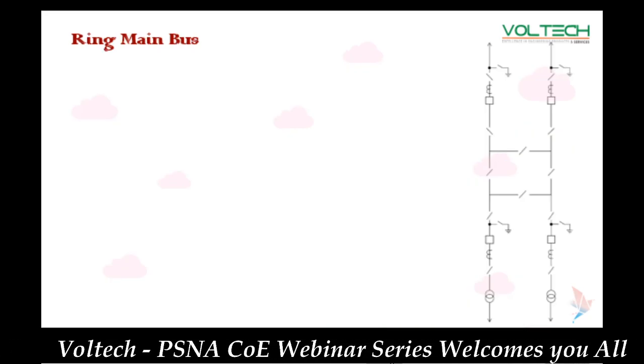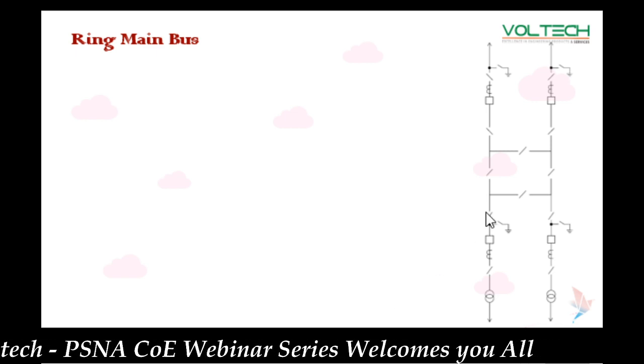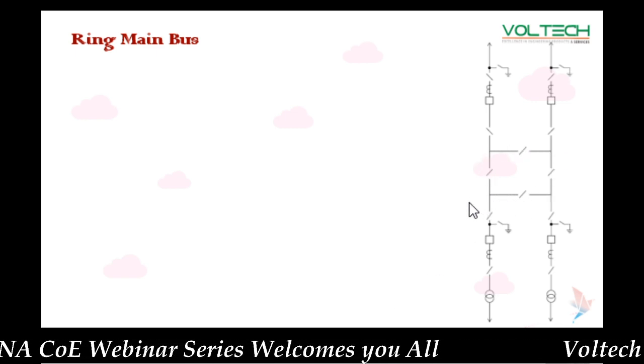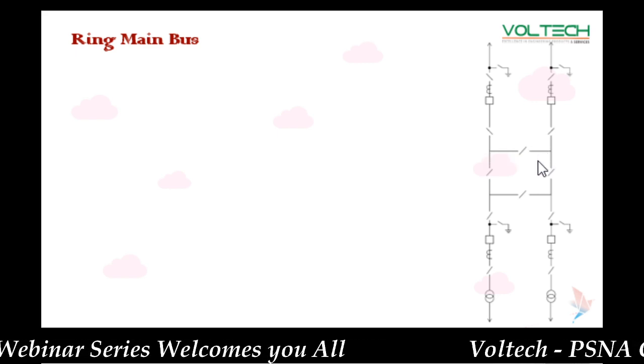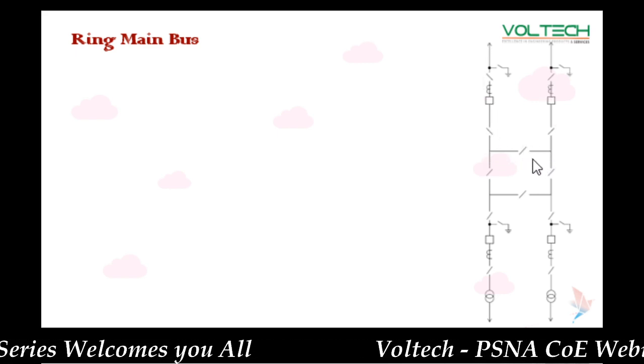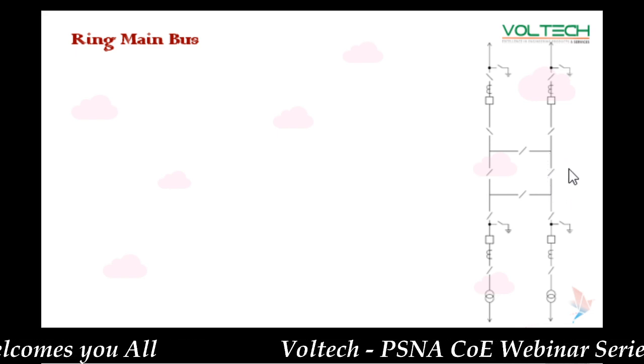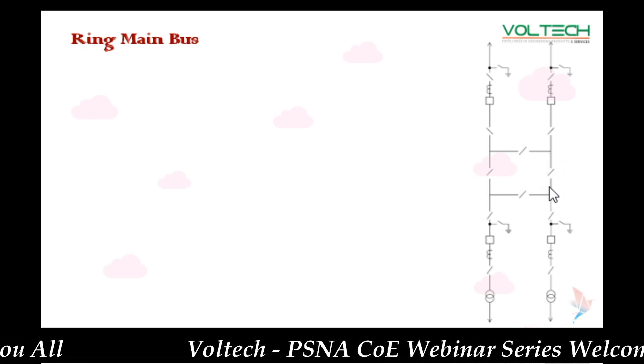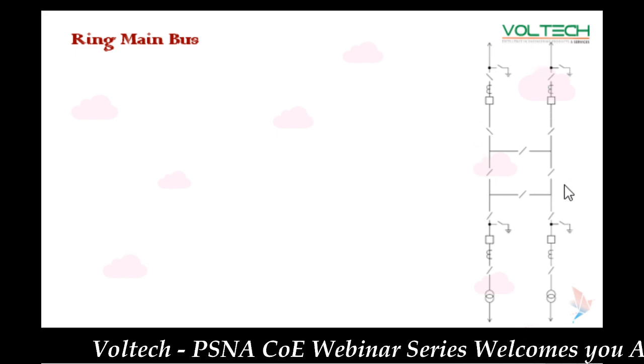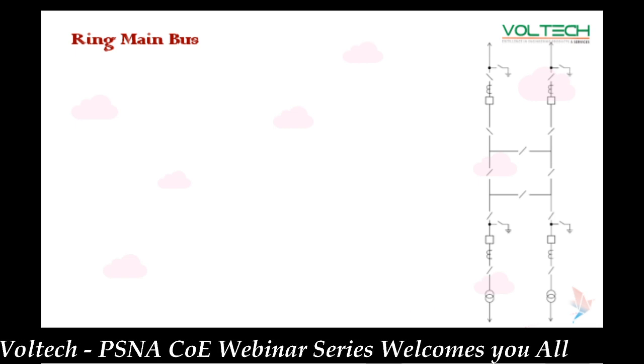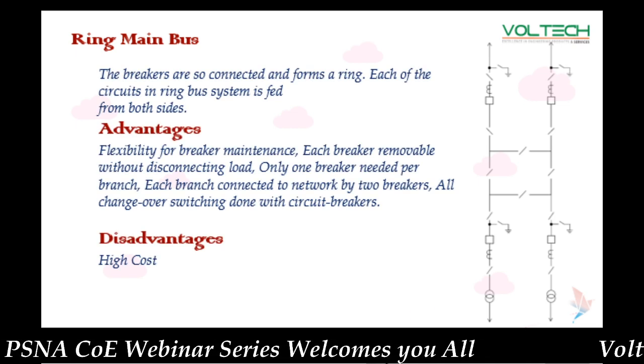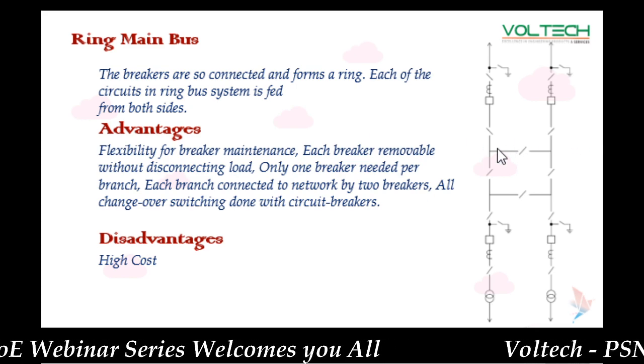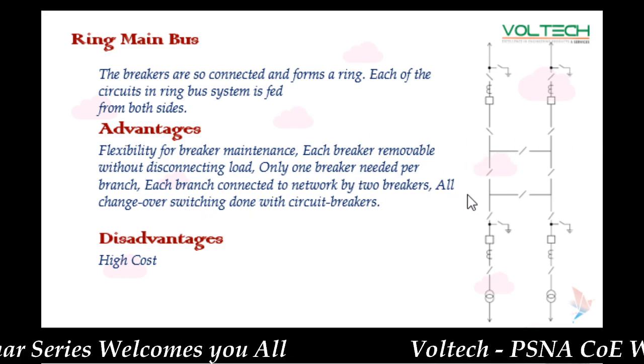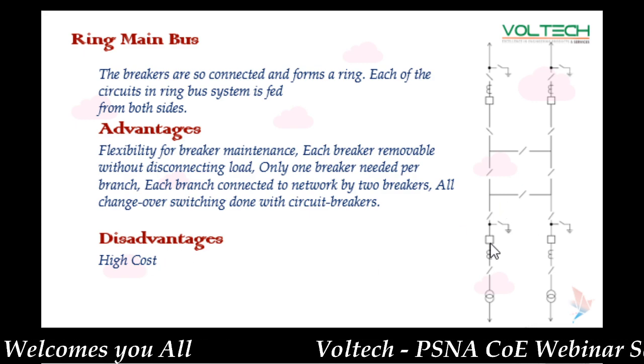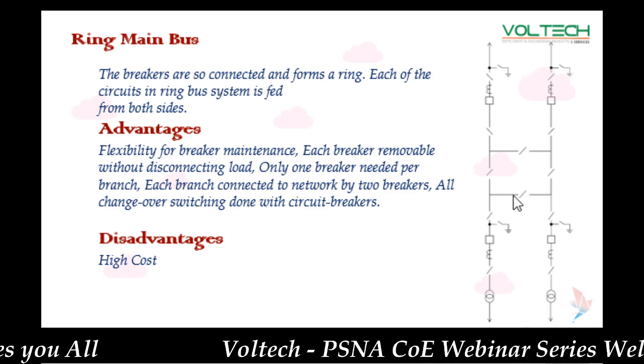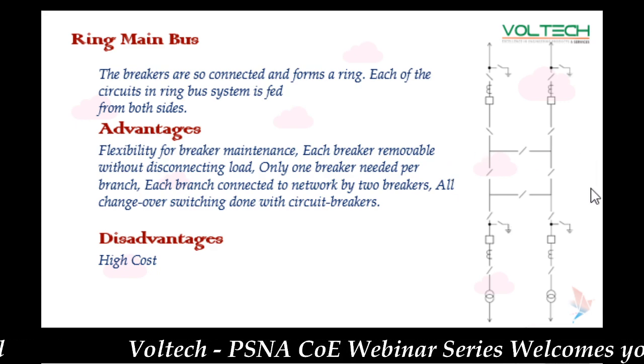So next is ring main. A ring main, I think all of you know, is a ring type of arrangement. You can get the power from any direction. Even if you want to do maintenance on this portion, I can shut it down without interruption of any other feeders. I can do the maintenance here. The advantage is that it is flexible for operation and easy for maintenance, but the disadvantage is high cost. Because of these arrangements, we have to invest more. We have to construct the ring type.